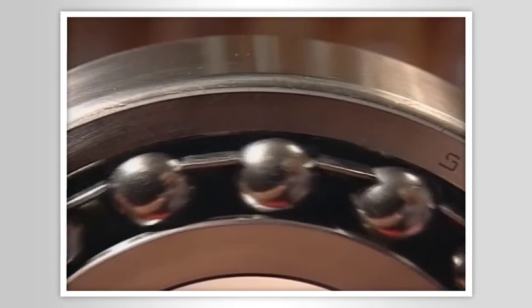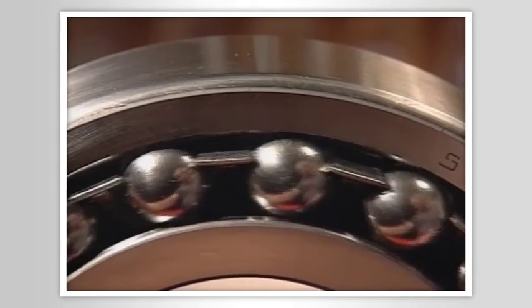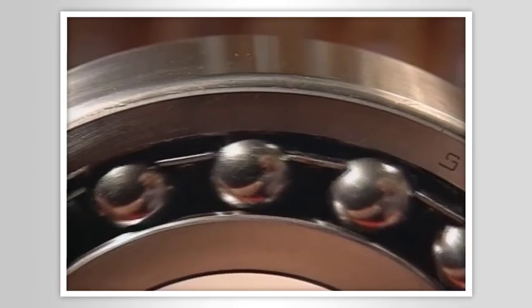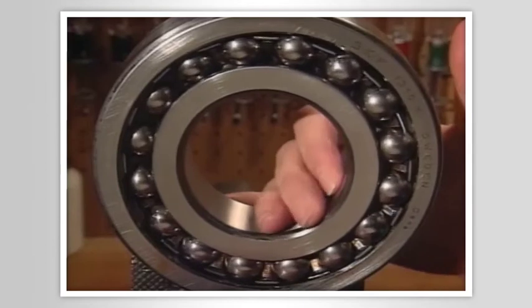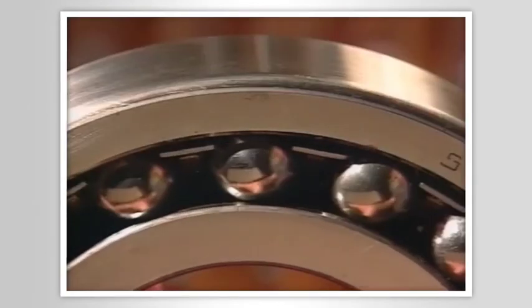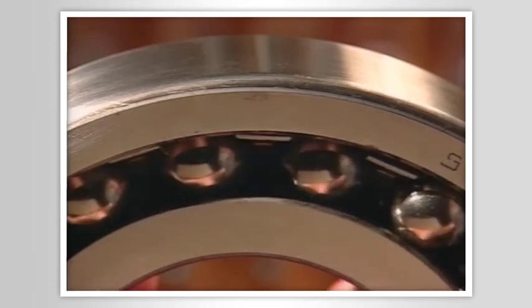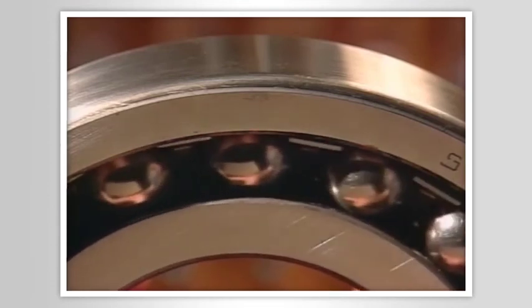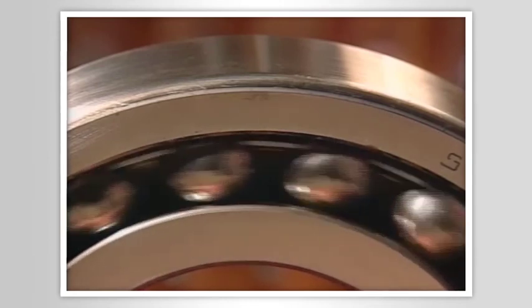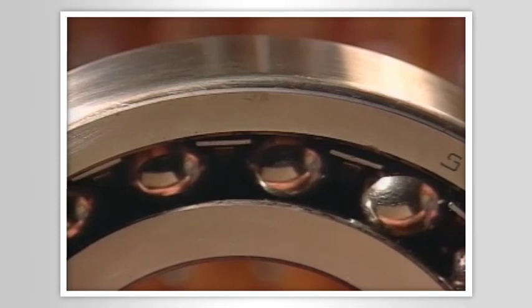Now let's look at a bearing with a more visible cage assembly. You'll notice that the cage and rolling elements are slowly working their way around the center of the bearing, in the same direction as the inner race. In the majority of industrial bearings, the cage will complete approximately 35 to 45% of one rotation with each rotation of the shaft. We would expect to find in the manufacturer's literature a multiplier less than 1. The manufacturer's multiplier, correctly known as the fundamental train frequency, is 0.44. In this particular bearing, the cage completes 44% of a rotation with each rotation of the shaft. If there is a defect in the bearing cage, a fundamental train fault frequency will be generated at 0.44 times shaft speed.